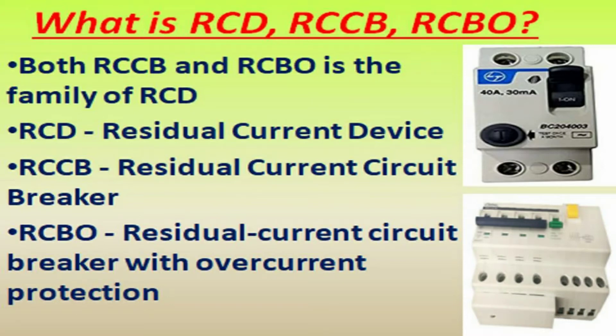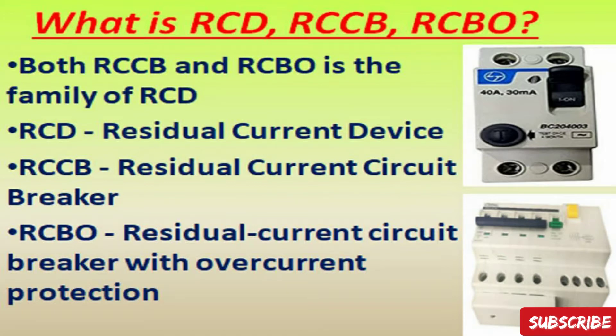Welcome to Gen in Papadia. In this video, I explain what RCD, RCCB, and RCBO are and how they work. Generally, RCD is a current-operated device, while ELCB is a voltage-operated device. Both RCCB and RCBO are part of the RCD family. RCD means residual current device, RCCB means residual current circuit breaker, and RCBO means residual current circuit breaker with over-current protection.